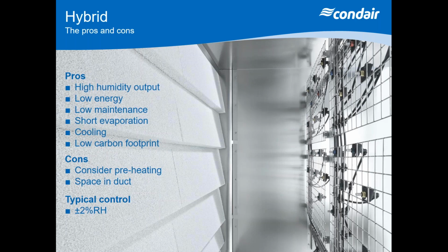So these can go from 7 stages up to 31 stages of control. So you've got very minute changes of output. And then you're going to have a spray, which is going to be switching these nozzles on, and you'll spray into the air, and anything that's not captured in that spray as part of the section will be evaporated off the media itself or the ceramic plates you're going to see. So this can give you low energy and close control at the same time. So in terms of maintenance, it's going to be a disinfection.